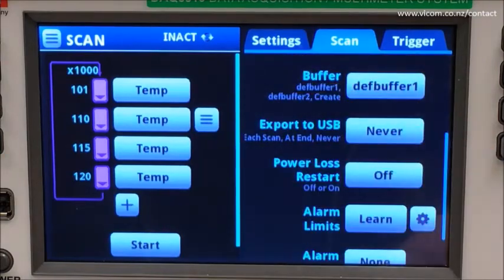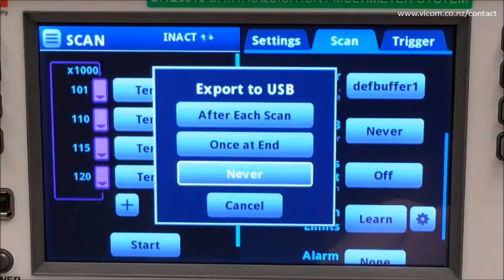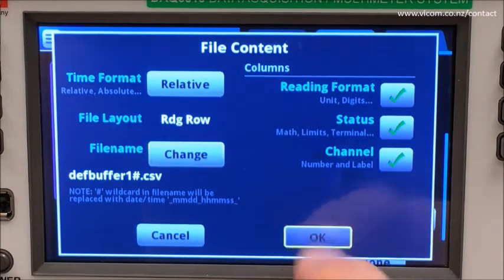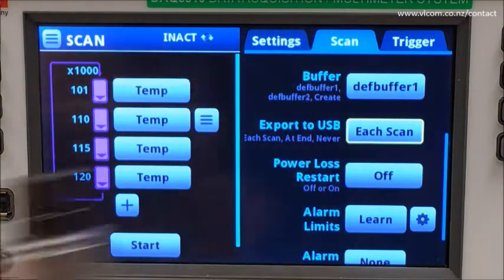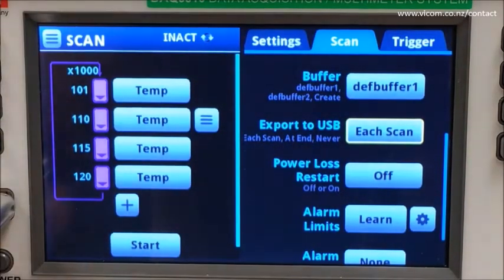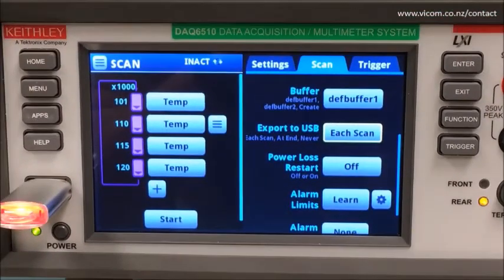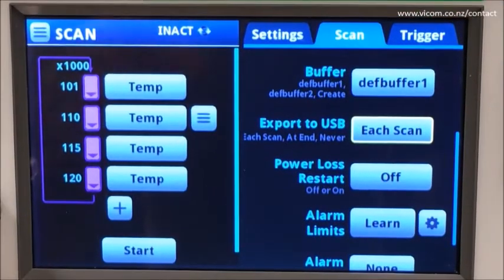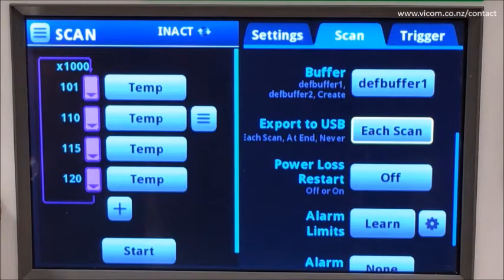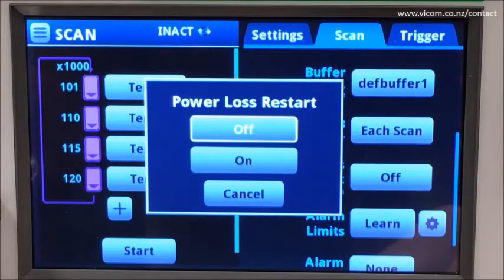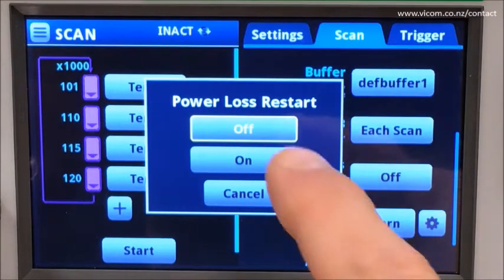During the scan, I wish to export the data after each scan to an external USB drive. I will accept all my file defaults, take my USB drive, and place it into the front of the DAQ-6510. And should the power go off sometime early in the 16-minute scan, I want it to restart from the very beginning without my intervention, so I will turn power loss restart on.